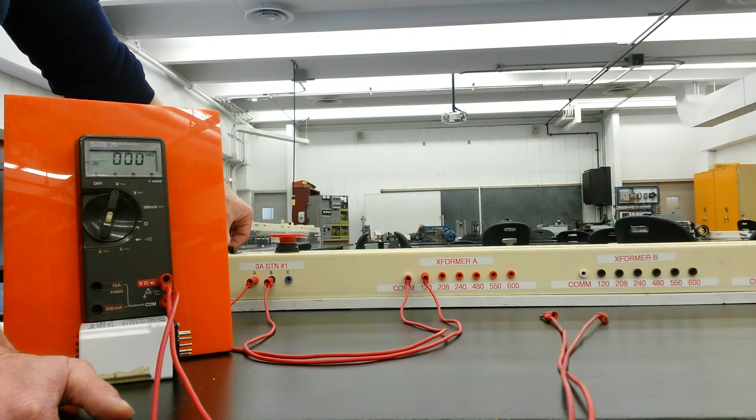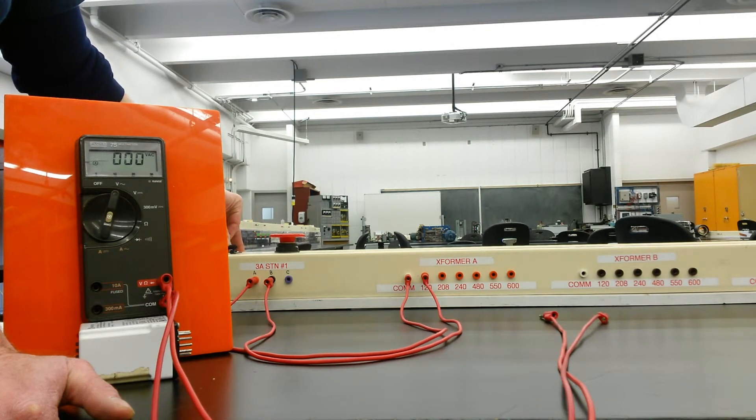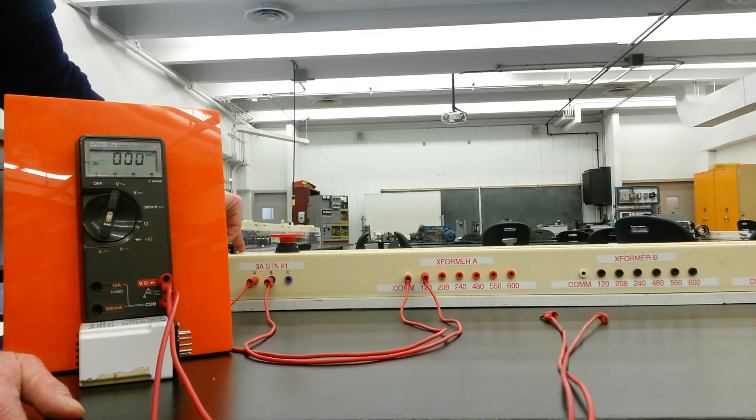So you can hear it consistently tripping. Okay, as try as I might, I cannot get this breaker to hold. Okay, you can actually see that, I don't know if you can make it out, but the wires are actually jumping a touch as I'm trying to close this breaker.